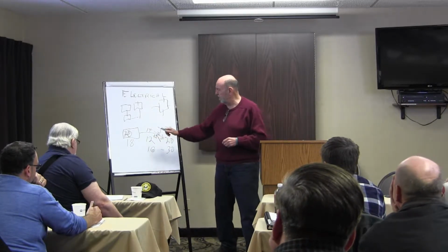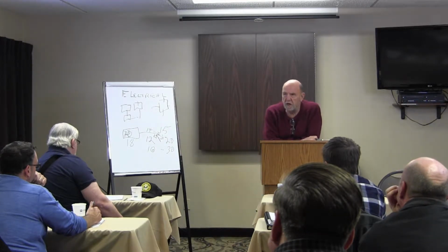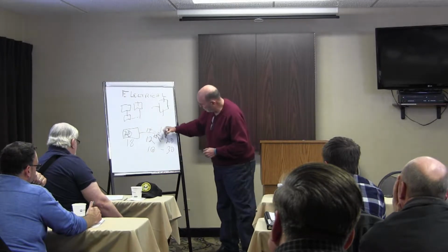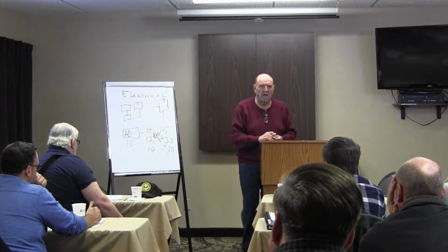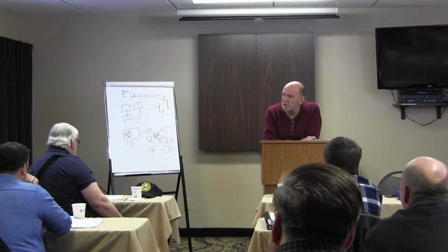I'm looking for a 14 gauge wire on a 20 amp breaker. That's the most common misuse. Now, I'm sure that there's some place where you would find a 14 on a 30, but I've never seen it. To make the search go a little quicker, I look at all my 20s and make sure there's no 14 on it.